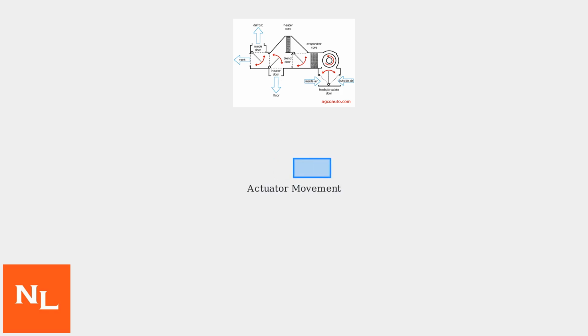Actuators, such as stepper motors, adjust airflow doors and flaps. They respond to control signals to fine-tune distribution, and synchronization ensures they operate precisely in unison for optimal performance. Synchronization ensures all these components work together harmoniously. However, problems often arise from sensor degradation or actuator failures, which can lead to imbalances requiring recalibration.